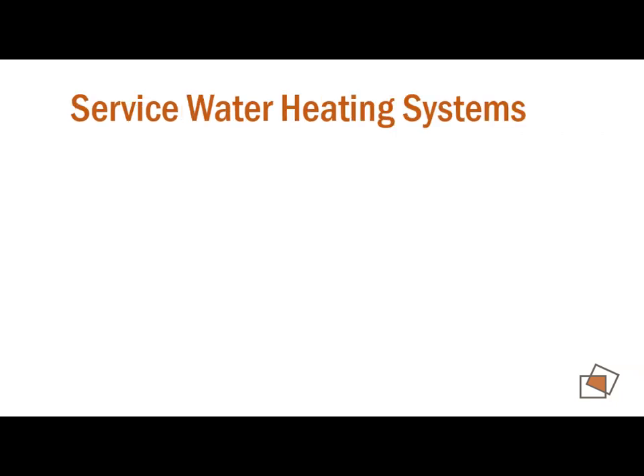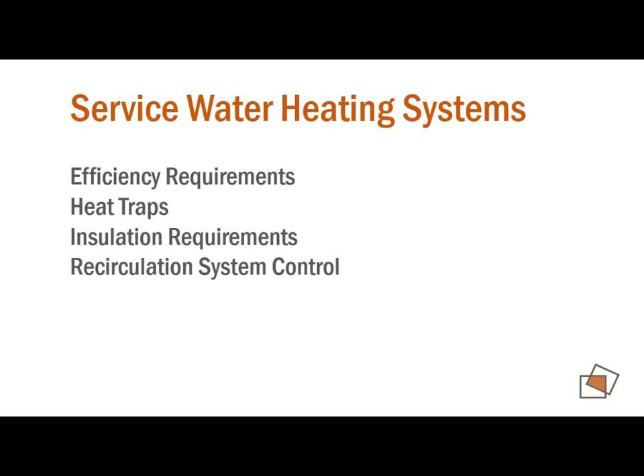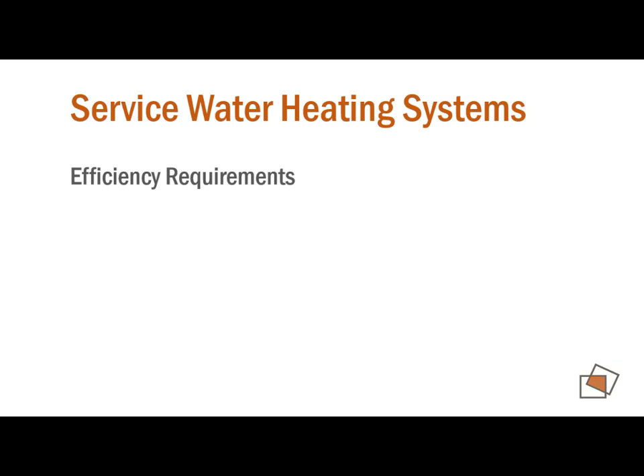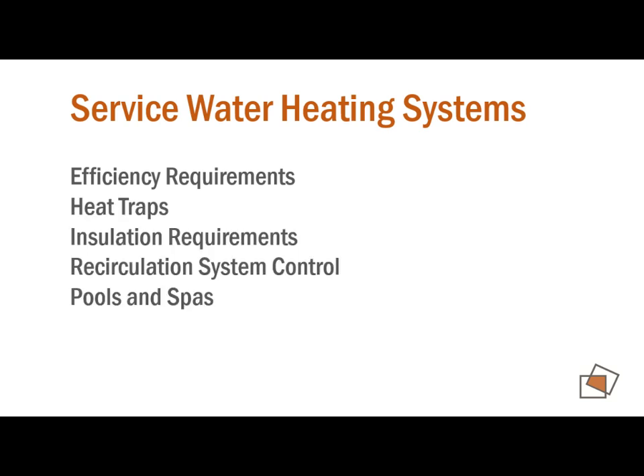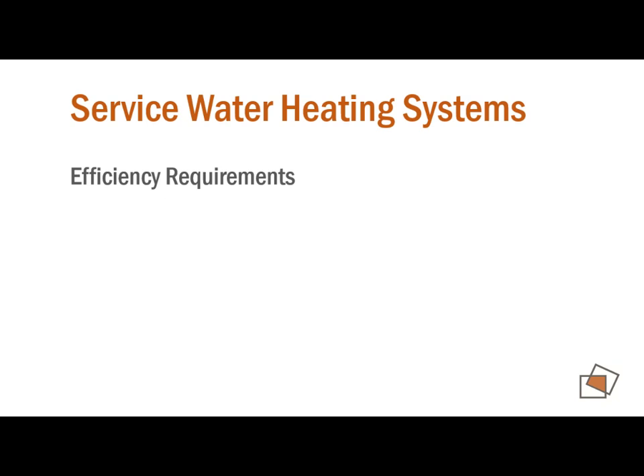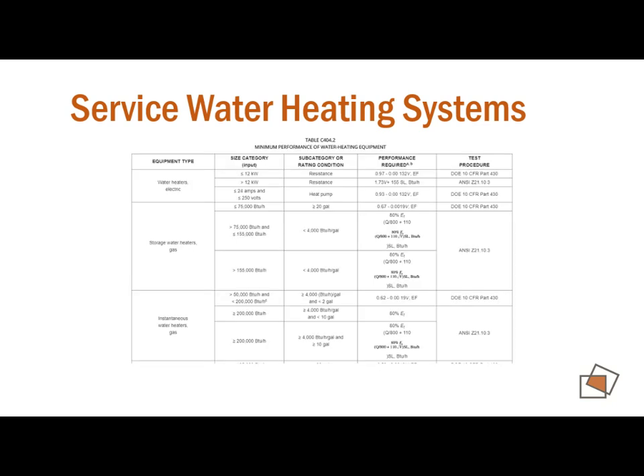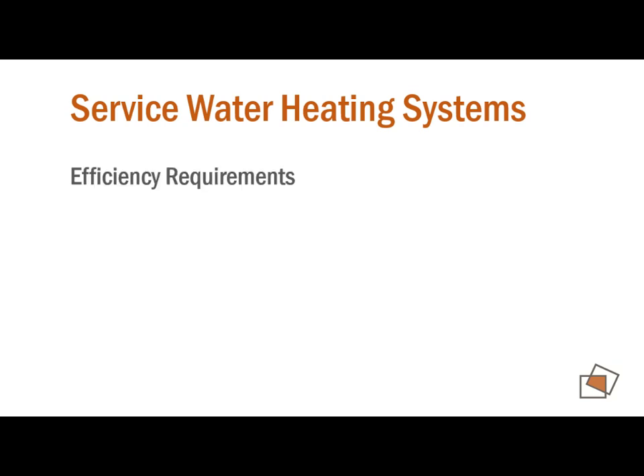Now I'll take a quick look at the water heating, and it has a handful of different requirements. So here's how the water heating system's broken up. Again, it's another chart with our efficiency requirements, and then it has some other specific items that we have to think about while we're designing. Here's that chart I talked about. So you can see here, electric water heaters, a certain kW cutoff, and it gives an energy factor rating that's required for that equipment. So anyway, there's a couple of charts in there associated with that.